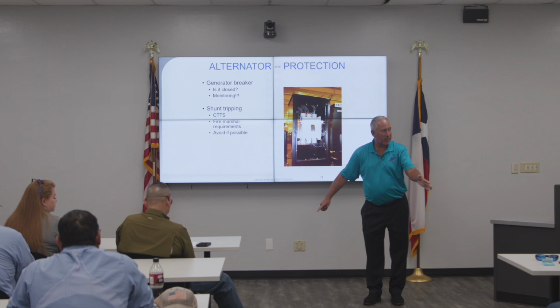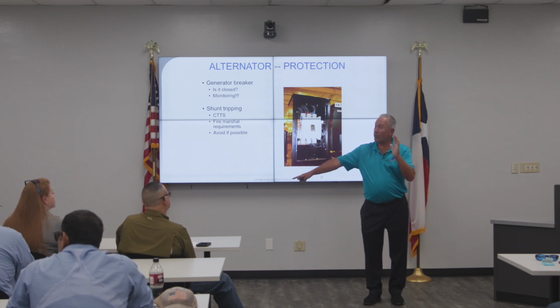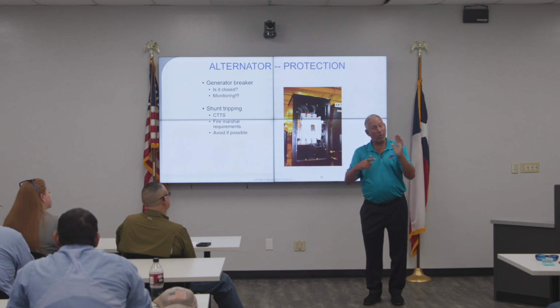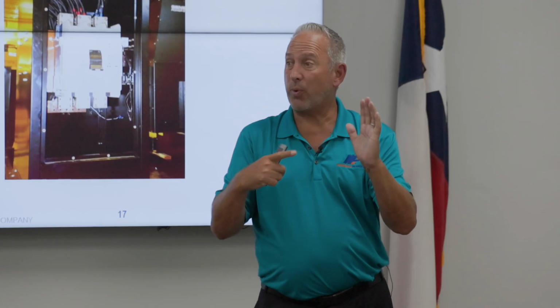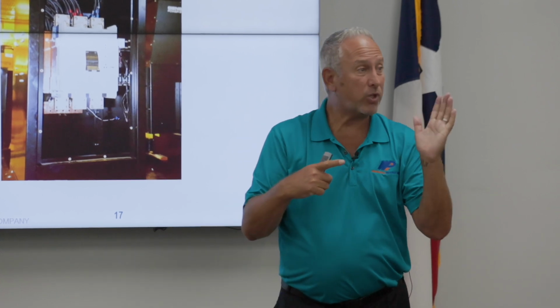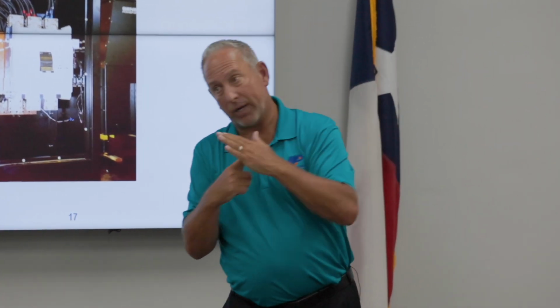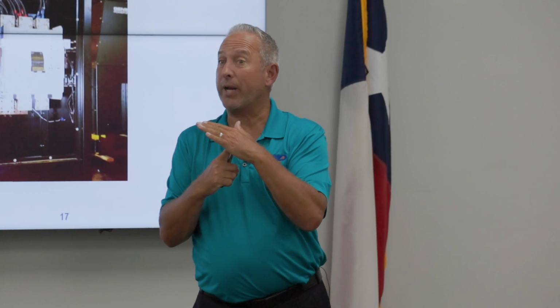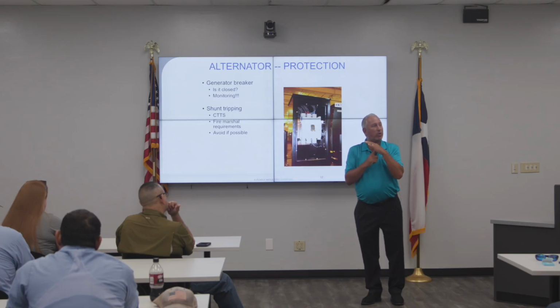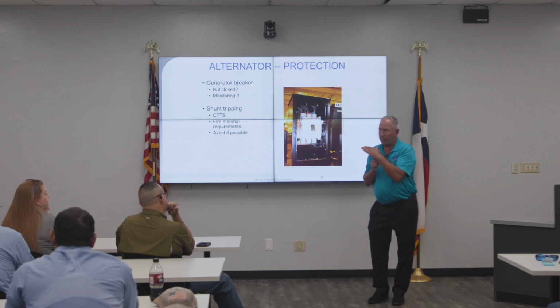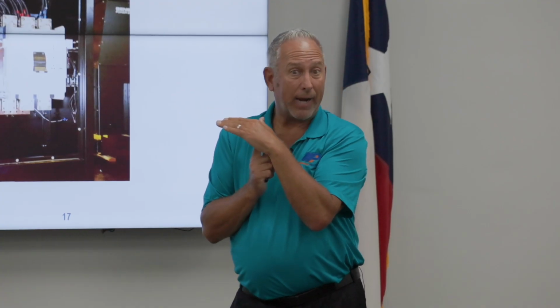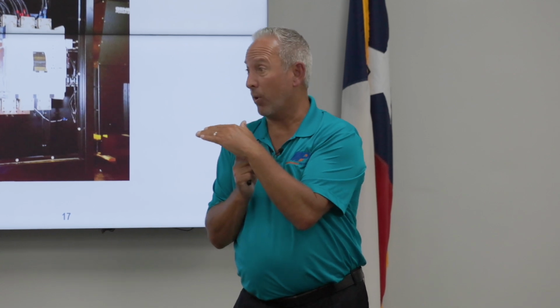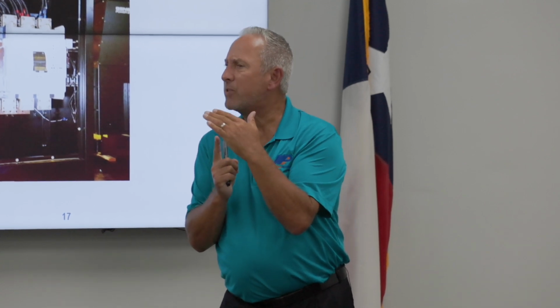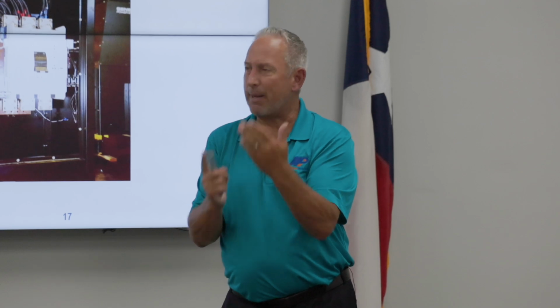So let's say the utility goes out, the switch sees it, it tells the generator to start, generator starts up, then the switch goes, oh, I see generator voltage here. It's within specification, so I'm going to transfer my switch onto the generator. And now you're powering the building, okay? So now utility comes back, and the transfer switch goes, oh, utility's back. And it's back for however long you set it for. Generally 15, 30 minutes. We want to make sure the utility is going to stay back.